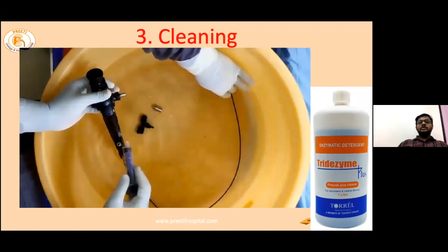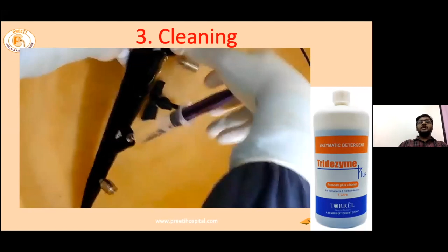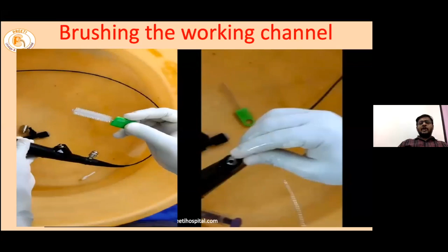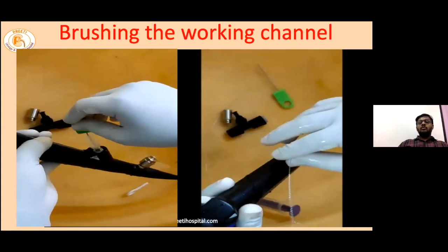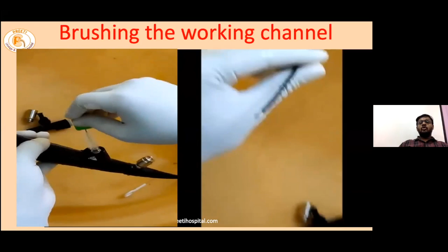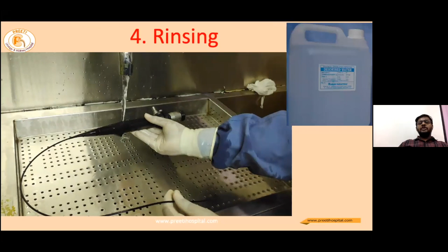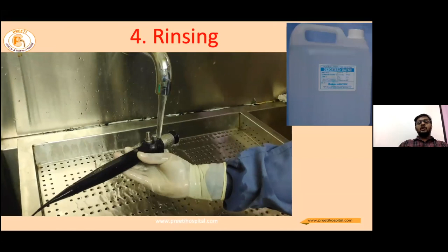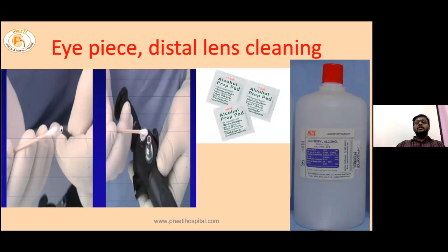In this cleaning, the scope is cleaned both interior and exterior with enzymatic solutions, using a 10 ml or 20 ml syringe, thoroughly flushed so that all the debris and blood inside the channels are washed out. Manufacturers also provide brushes of various shapes and sizes to clean all the valves and channels, and it is important to clean all those channels before disinfection. After cleaning, all residual debris should be washed out in a process called rinsing. In this rinsing, we commonly use deionized water, distilled water, or tap water. Special care should be taken to clean the eyepiece and the distal lens. Commonly, we use 70% isopropyl alcohol, and either disposable swabs or wipes are available.